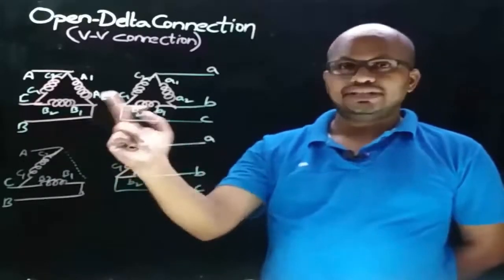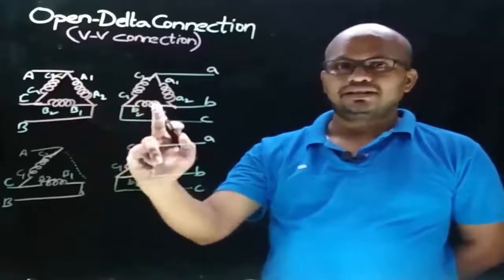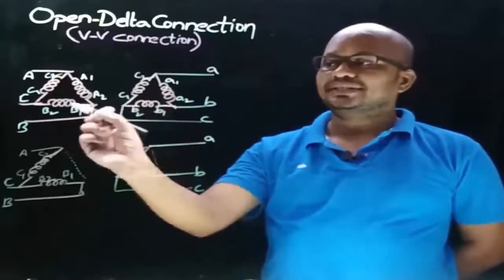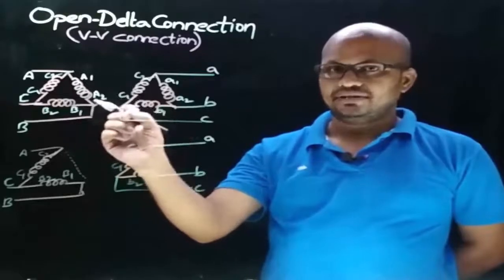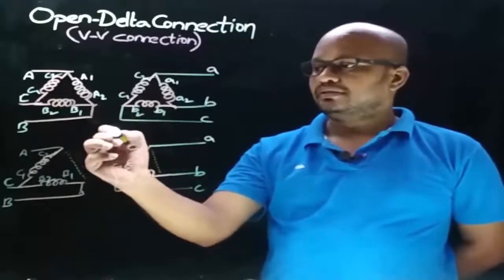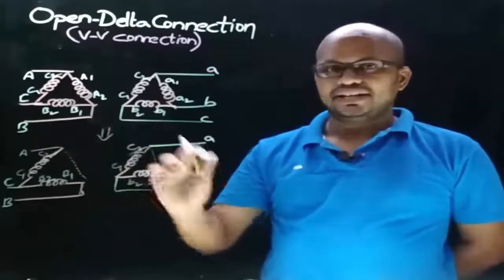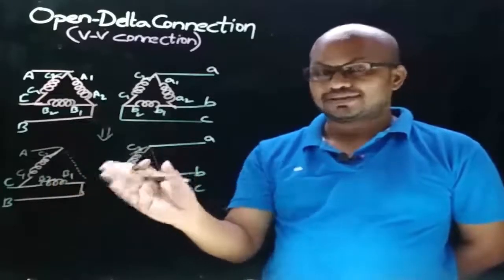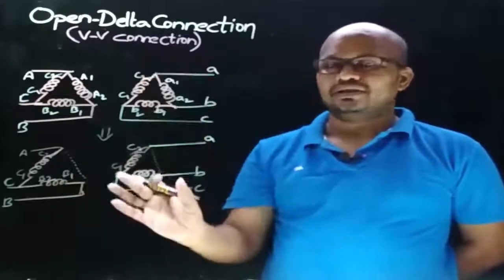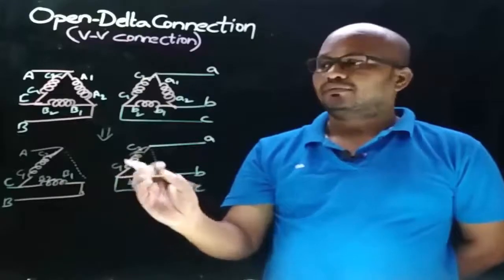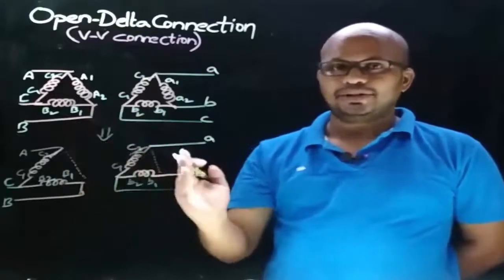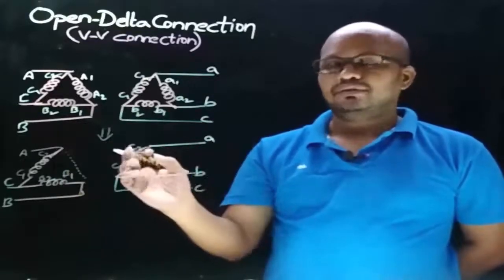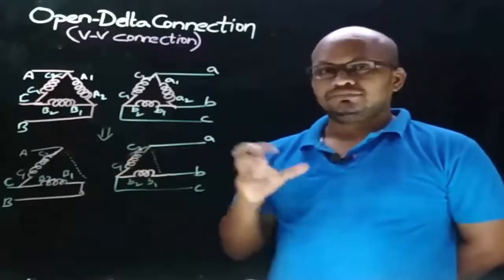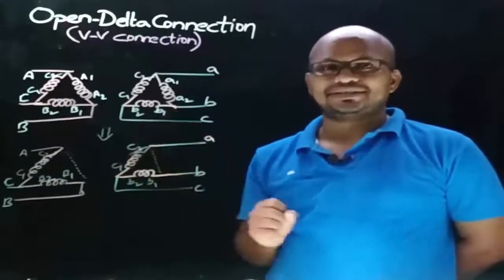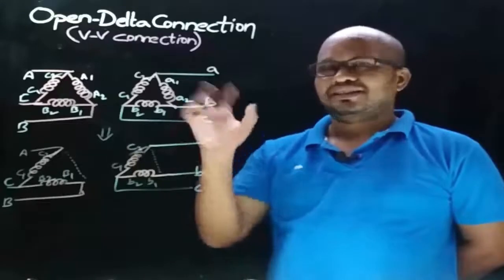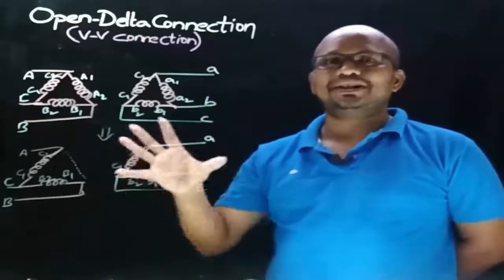So when one of the transformers in a delta-delta connected single phase 3 transformer bank gets failed, then the resultant winding connection is called open delta connection. And with this open delta connection, we can maintain the continuity of supply to the load, but with reduced capacity. Now let's know the reduced capacity. That is, let's know the kVA rating of open delta connection.